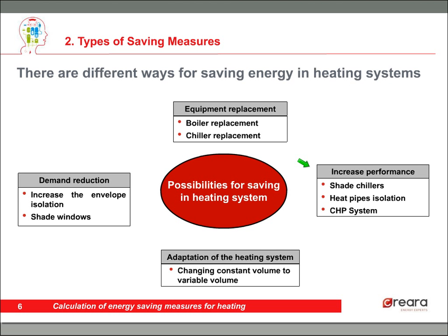We also have increase of performance without the need of installing fully new equipment, such as shading chillers to reduce the temperature at which thermal exchange takes place, heat pipe insulation, or a full installation of a CHP system, which involves a huge increase of performance and saving of primary energy. And finally, adaptation of the heating system — some adaptations to match demand to building activity, such as changing constant volume to variable volume for secondary heating circuits.